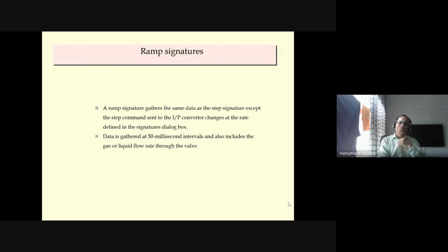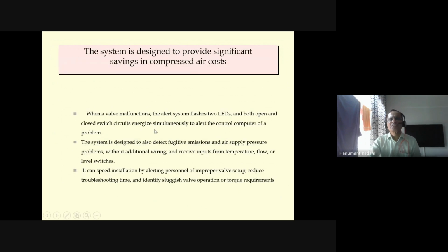Ramp signatures. A ramp signature gathers the same data as the step signature, except the step command sent to the I/P converter changes to the rate defined by the signature dialog box. Data is gathered at a 50 millisecond interval and also includes the gas or liquid flow rate through the valve. The system is designed to provide significant savings in the compressed air cost. One of the applications is mentioned here, benefits achieved in compressed air.